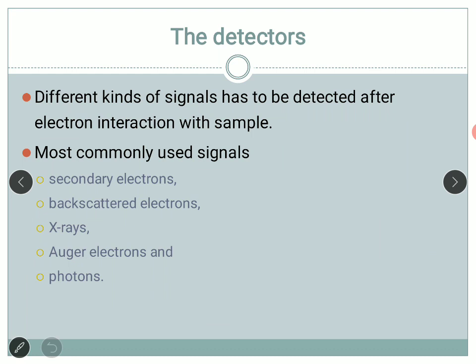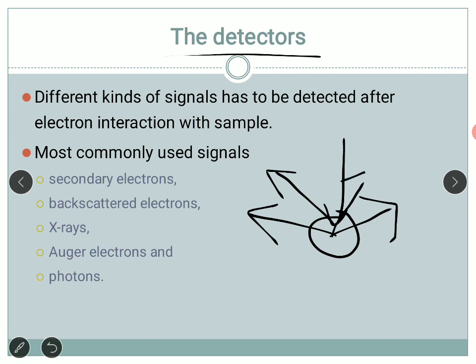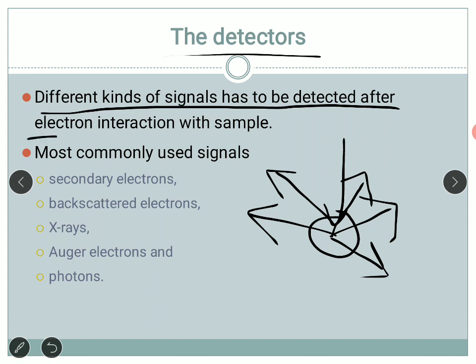We now need to know about the different kinds of detectors. After the condenser and objective lenses focus the beam and the scan coils raster the sample, signals are deflected from the sample and must be detected. When an electron beam is incident on a sample, a number of processes happen: we get secondary electrons, backscattered electrons, X-rays, photons, and Auger electrons. For each of these signals we need a separate detector because their intensity and energy will differ.